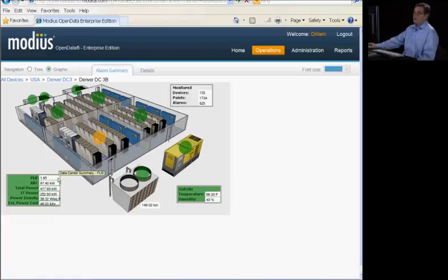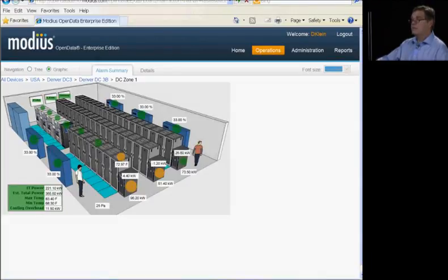But on this screen, we can also get some metric or key performance indicator information, such as the overall efficiency of the location, the available redundant capacity, the current cooling tonnage on the chiller, as well as other types of information such as total power consumed and IT power consumed. If we drill into a specific location, you can see that in this zone we have the capacity utilization for the perimeter cooling units being tracked.